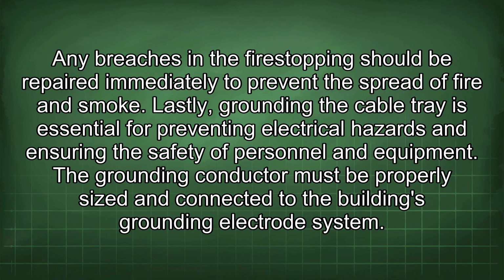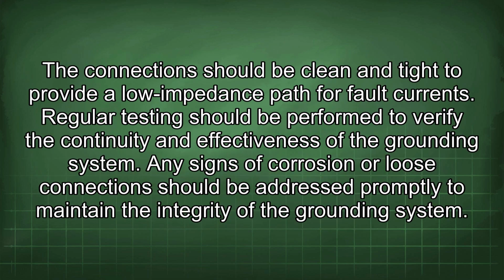Lastly, grounding the cable tray is essential for preventing electrical hazards and ensuring the safety of personnel and equipment. The grounding conductor must be properly sized and connected to the building's grounding electrode system. The connection should be clean and tight to provide a low impedance path for fault currents. Regular testing should be performed to verify the continuity and effectiveness of the grounding system. Any signs of corrosion or loose connection should be addressed promptly to maintain the integrity of the grounding system.